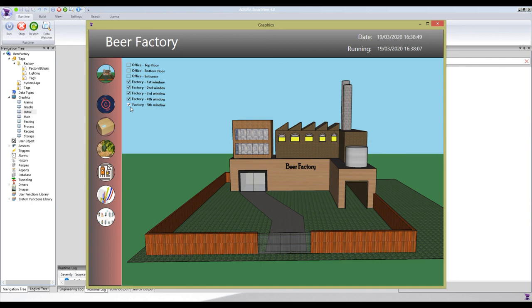And that's it. I just wanted to show you how to configure the checkbox, and of course this is just a demo. In real life you would have to use the same tags that we used on the checkboxes and on the IsVisible property to also communicate to probably a PLC using OPC, or maybe a driver using a specific protocol to get the information and actually turn on and turn off the lights. But since this is just a demo, I'm not creating any communication, and maybe in the future we can do it using a driver. Okay?